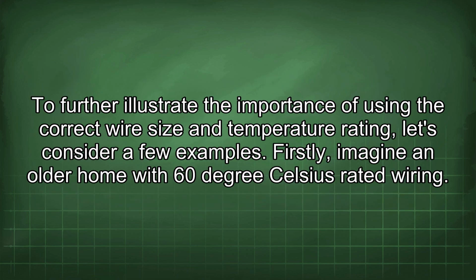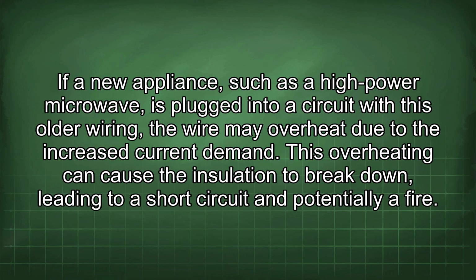To further illustrate the importance of using the correct wire size and temperature rating, let's consider a few examples. Firstly, imagine an older home with 60 degrees Celsius rated wiring. If a new appliance, such as a high-power microwave, is plugged into a circuit with this older wiring, the wire may overheat due to the increased current demand. This overheating can cause the insulation to break down, leading to a short circuit and potentially a fire.